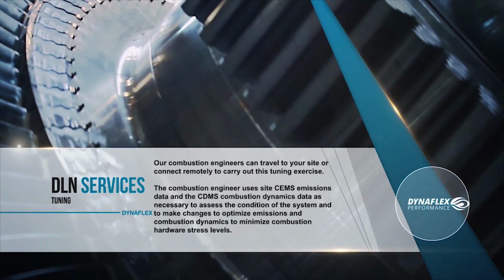Our combustion engineers can travel to your site or connect remotely to carry out this tuning exercise. The combustion engineer uses site CEMS emissions data and CDMS combustion dynamics data as necessary to assess the condition of the system and to make changes to optimize emissions and combustion dynamics to minimize combustion hardware stress levels.